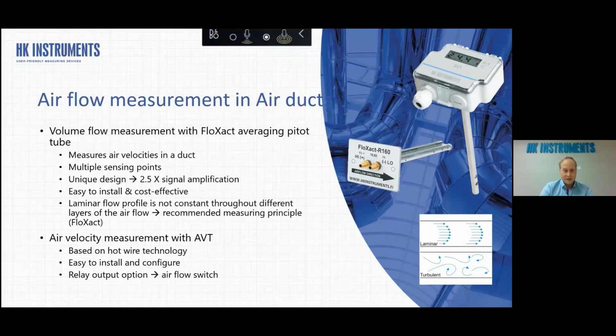But my recommendation is always to choose this multiple point probe, which is the FloXact, because you can see on the picture the flow profile. Even if the airflow is laminar, there is still variation for the air velocity. And if you're using 1 point measurement, you just get only the 1 point velocity. But the multiple point senses these multiple velocities, and then it's averaging those. So the result will be more accurate.